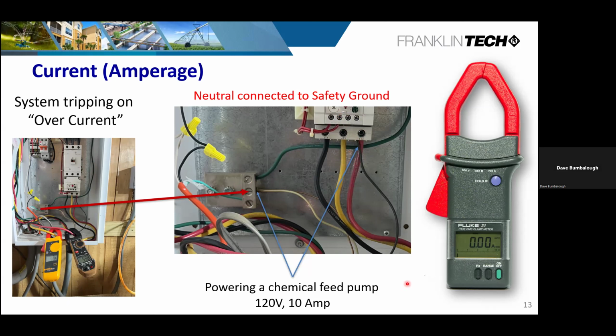We also run into situations where, in the pump house, somebody goes in behind the contactor and says they want to put a light in there, or plug up a fan or some kind of heating element. Well, they end up tapping off the power supply and just pulling off one leg, and then they take the return back to the safety ground instead of a dedicated neutral, especially if it's a 115-volt load. The neutral is designed to carry current, not the safety ground. The safety ground is there to cause the overload protection to trip. And if we're using that, then we're energizing the system, so we can cause potential shock hazards at this point. So we want to be very careful there.